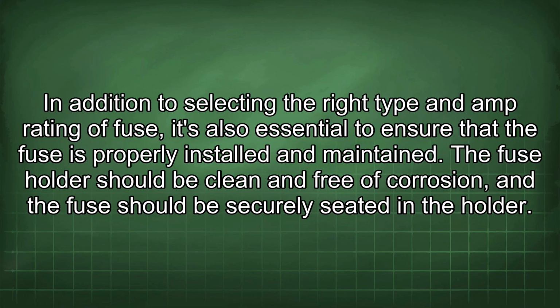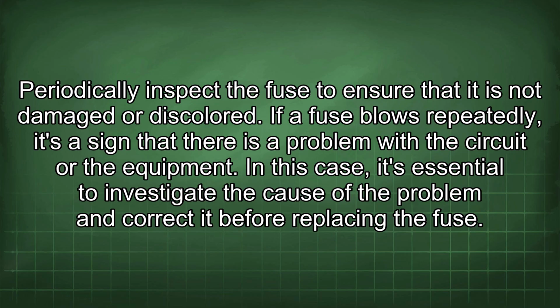In addition to selecting the right type and amp rating of fuse, it's also essential to ensure that the fuse is properly installed and maintained. The fuse holder should be clean and free of corrosion, and the fuse should be securely seated in the holder. Periodically inspect the fuse to ensure that it is not damaged or discolored.